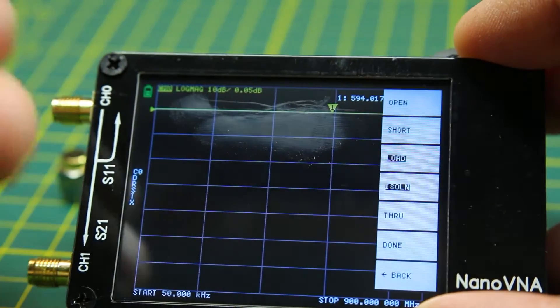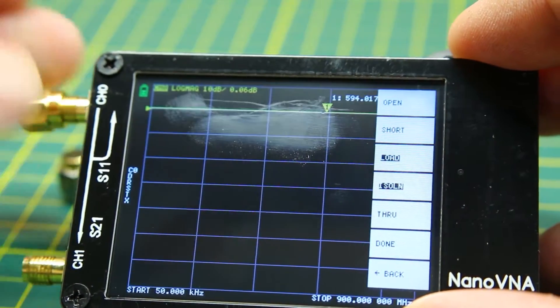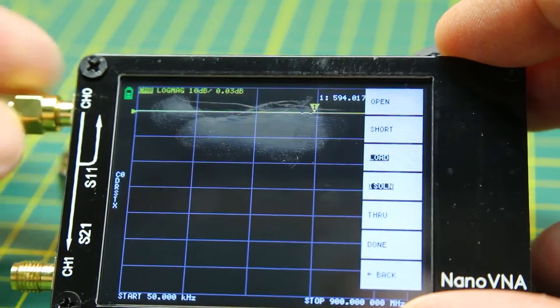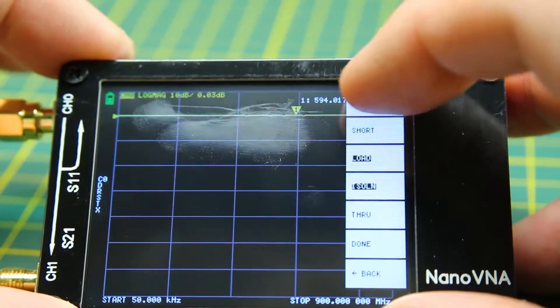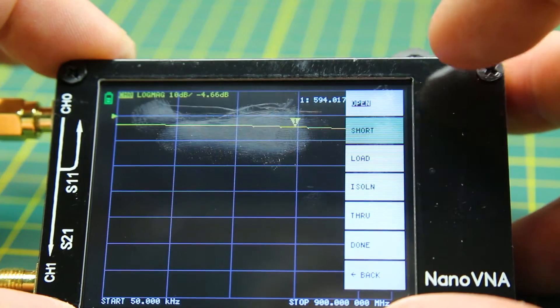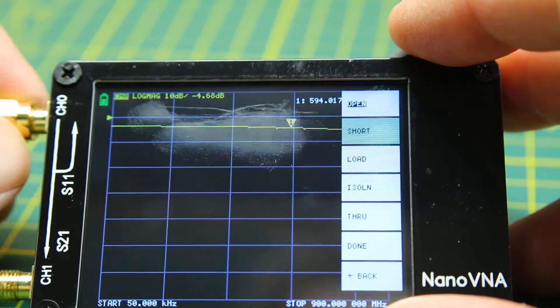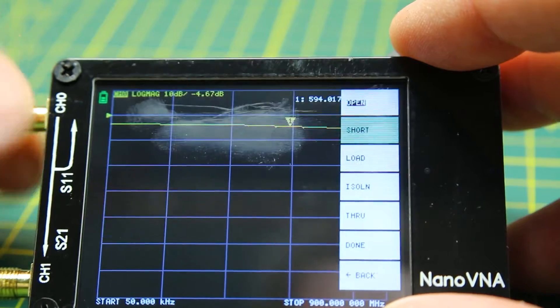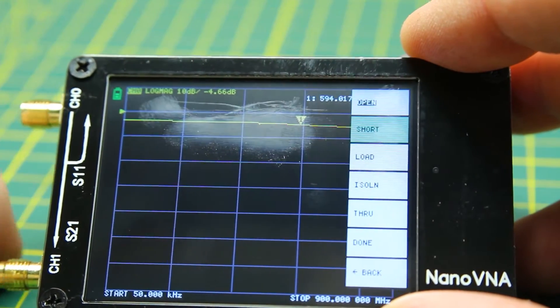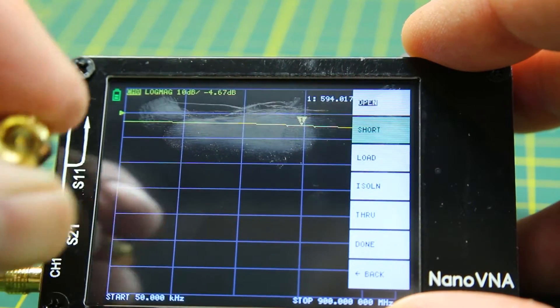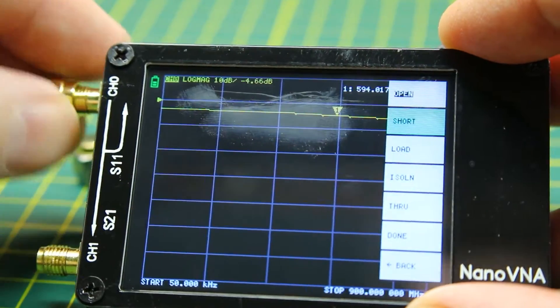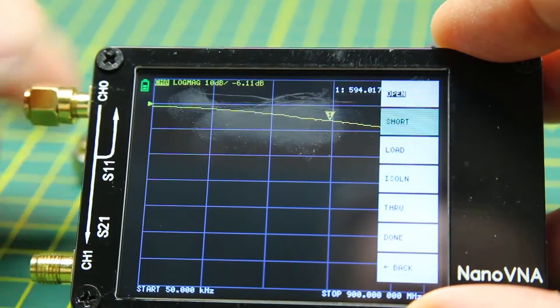Pretty much the only gotcha to using these things is any time you change your span, or your size of your display, or what frequencies you're looking at, you need to run a calibration, or recall a calibration that you've done for that exact same setup. Otherwise you're not going to get the sampling across the screen or the display resolution that you would if it was properly calibrated.